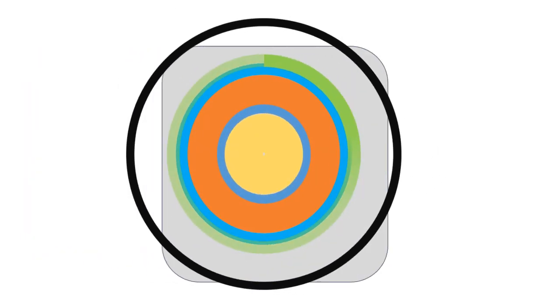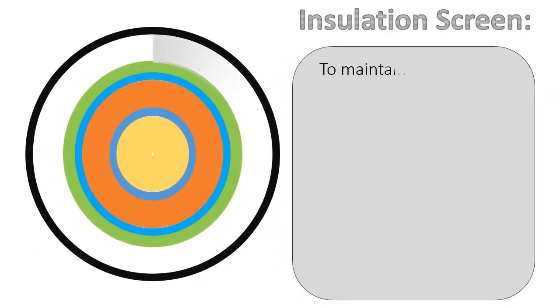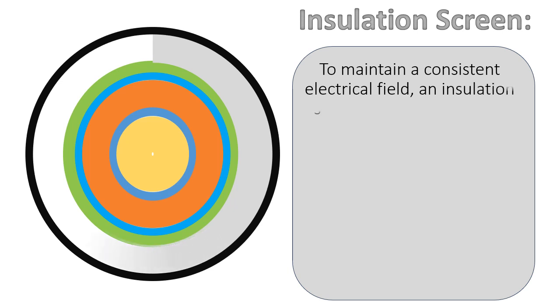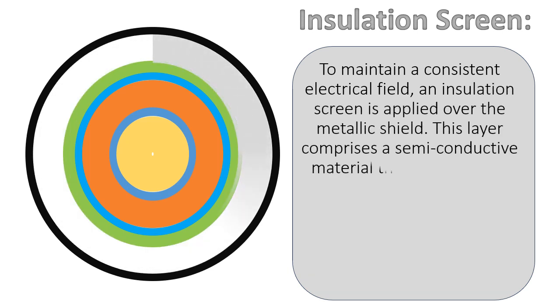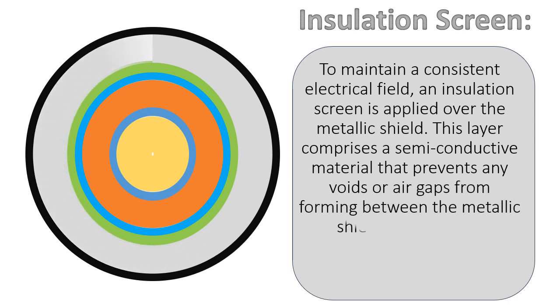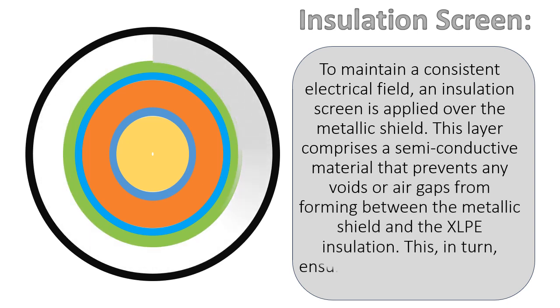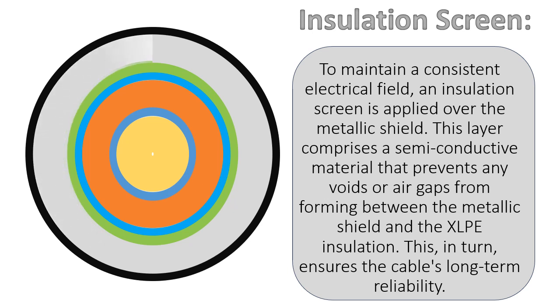Insulation screen: To maintain a consistent electrical field, an insulation screen is applied over the metallic shield. This layer comprises a semi-conductive material that prevents any voids or air gaps from forming between the metallic shield and the XLPE insulation. This, in turn, ensures the cable's long-term reliability.